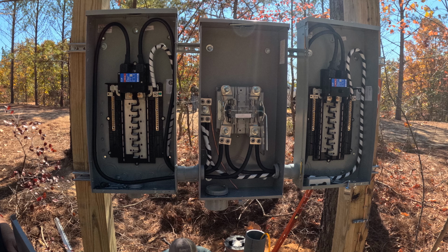So step 1, put the post in the ground. Step 2, put the unistrut in and mount the boxes, and connect them together with a little piece of conduit between the meter base and both of the disconnects. That's step 2.